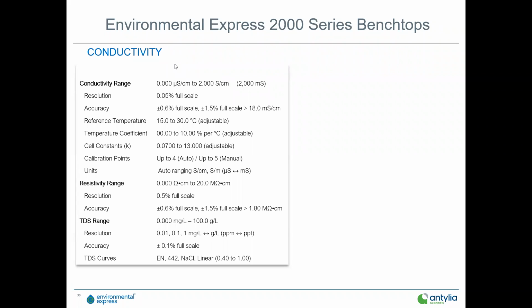And then we'll quickly touch on the electrical conductance, 0 to 2000 millisiemens. So this is a full range electrical conductance measurement. Any conductivity measurement you could think of, you can do with this instrument. It's got excellent accuracy, again, plus or minus 0.6%, 1.5% full scale above 18 millisiemens. Still, again, excellent accuracy. Reference temperature is adjustable, temperature coefficient, cell constant, up to 4 cal points, 5 points manually. Resistivity 0 to 20 megaohms. TDS is 0 to 100 grams per liter. And again, these are all auto ranging with good resolution in each of the ranges.